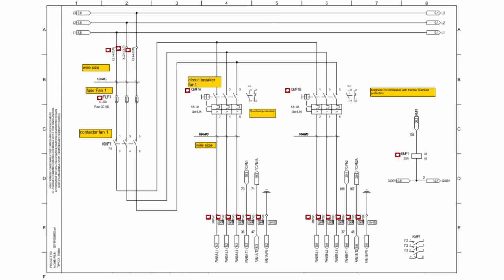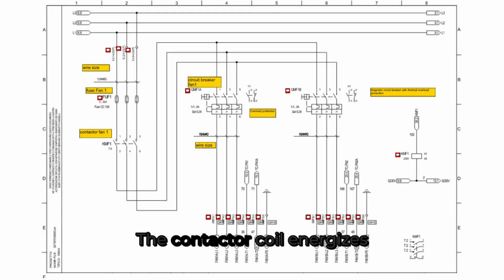Downstream of the fuses, the circuit connects to the fan contactor, labeled KMF1. This contactor acts as a high-voltage switch that energizes the fan motor when the controller calls for fan operation. The contactor coil is energized by 230 volts, which is indicated on the same page, column 8. Coil control input comes from a relay output of the control board.